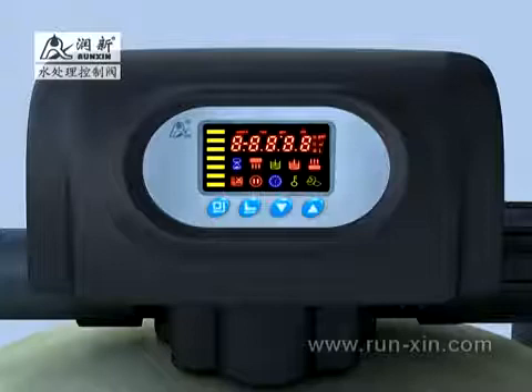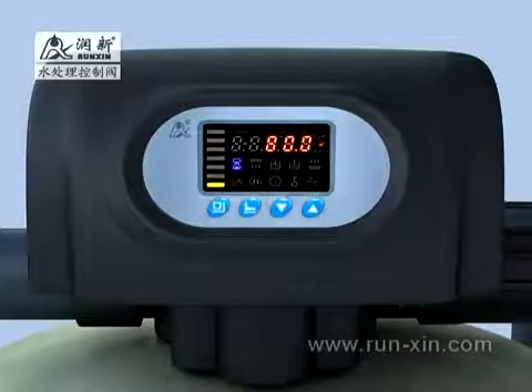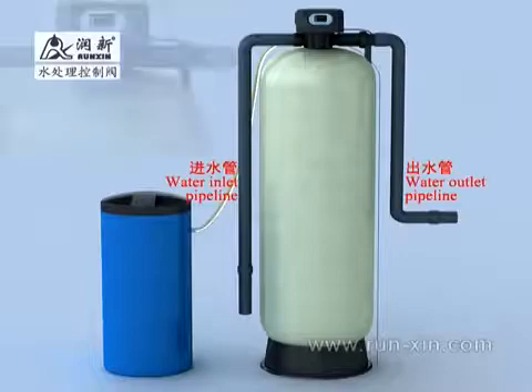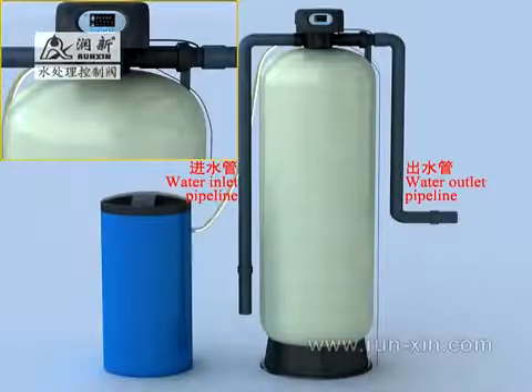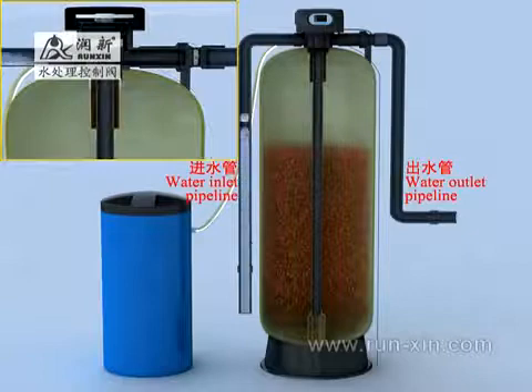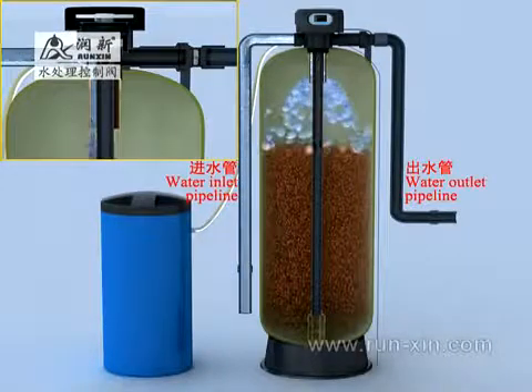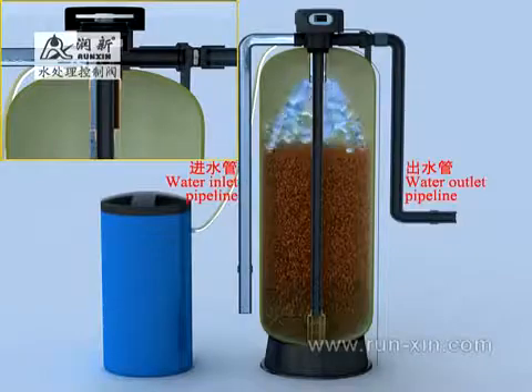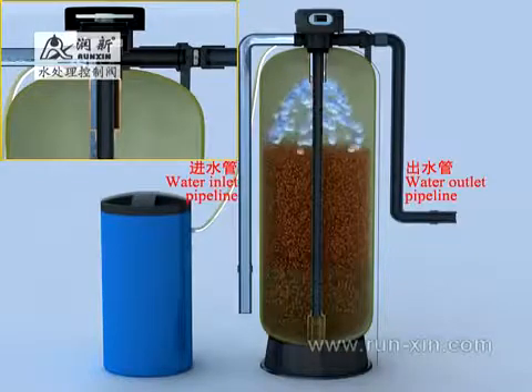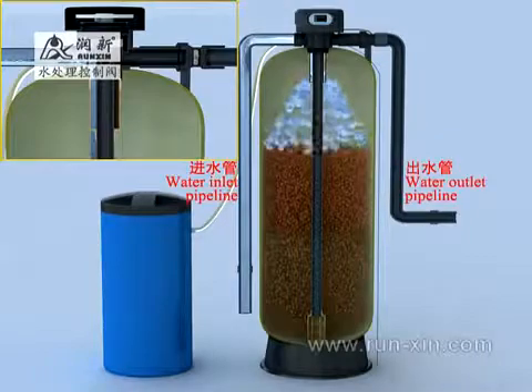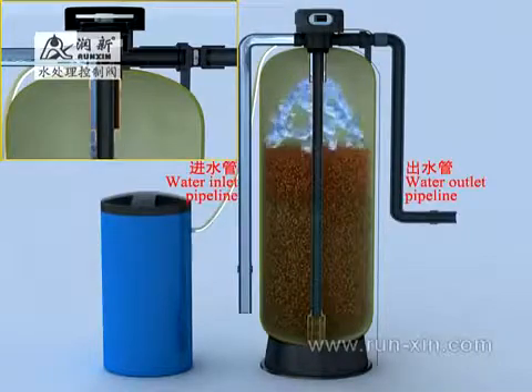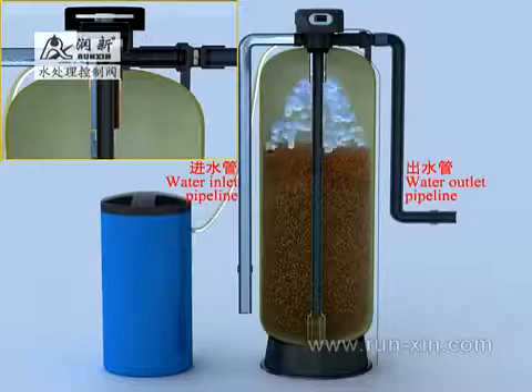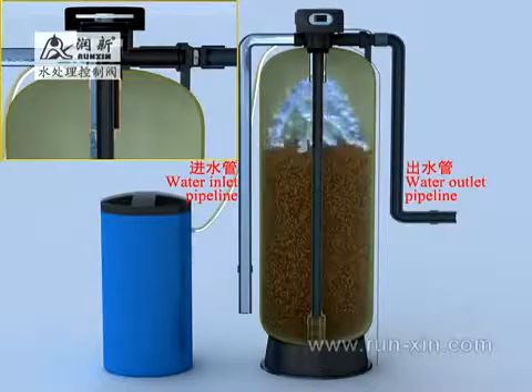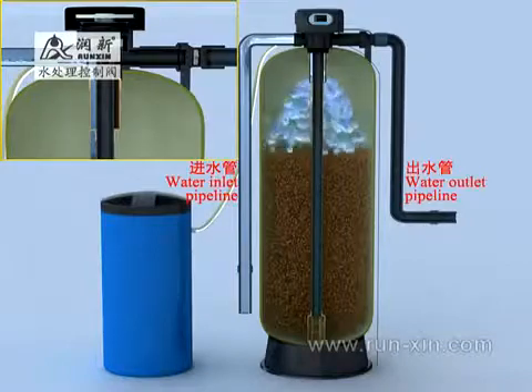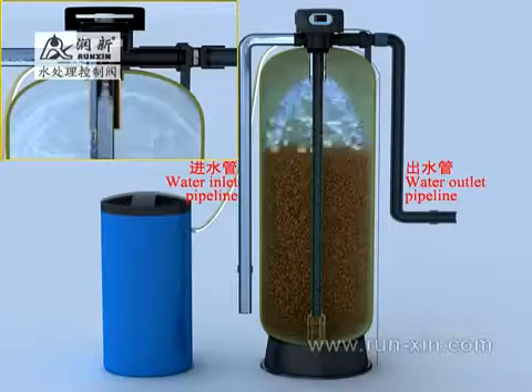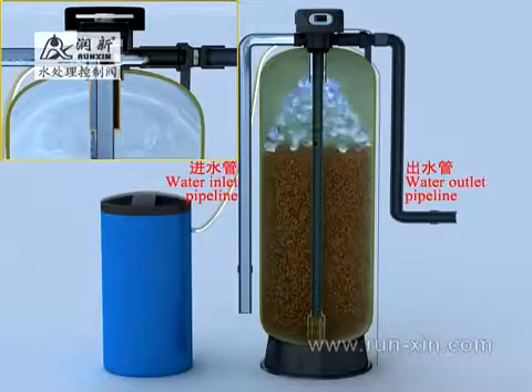When the system is in service state, the symbol of service state lights. At this moment, raw water flows into the control valve through the water inlet, from the top of the valve core to the valve body, and through the top strainer to the tank. Then down through the resin layers to become softened water. Through the bottom strainer to return to the riser pipe and valve core. Finally, it flows out from the water outlet.